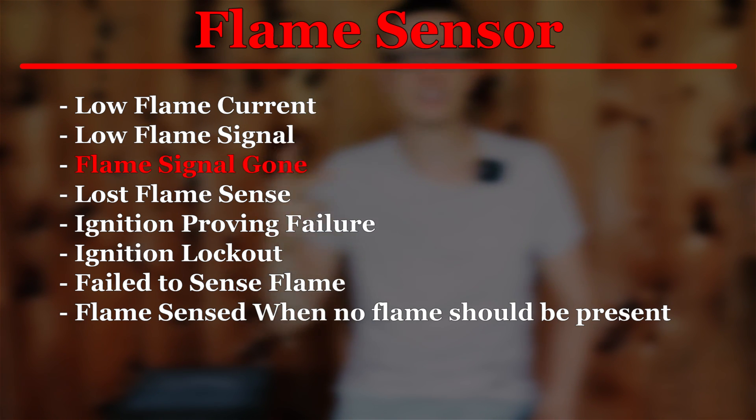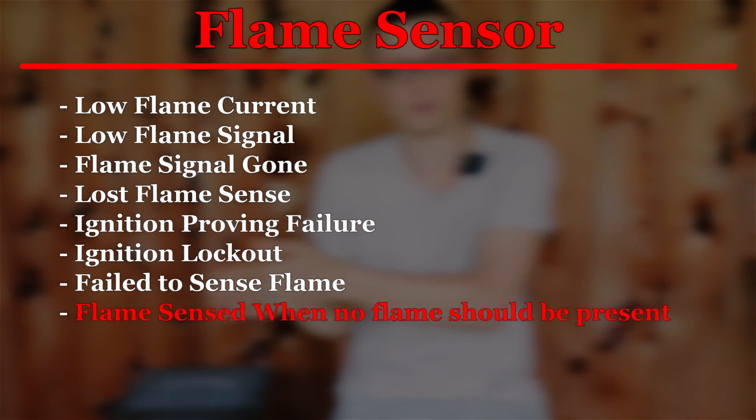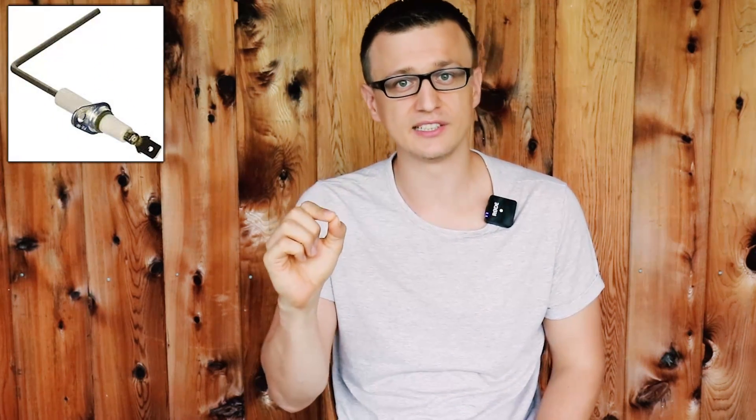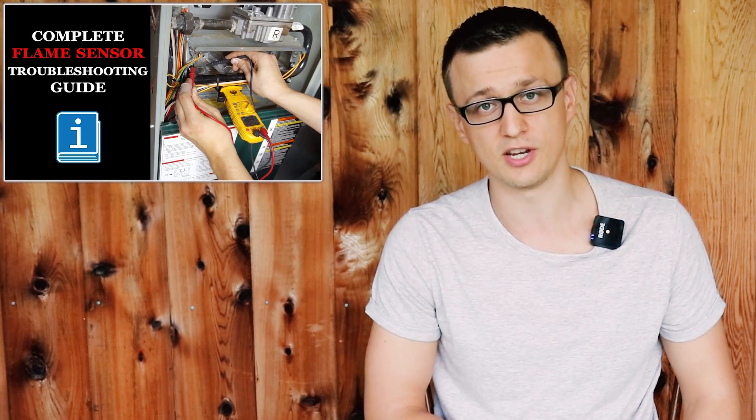The first error code I want to cover is the most common problem I run into, and luckily this one is usually the most easiest problem to fix — and that is the flame sensor error code. On different furnaces this error code will be worded differently, but here are some examples: low flame current, low flame signal, flame signal gone, lost flame sense, ignition proving failure, ignition lockout, failed to sense flame, flame sensed when no flame should be present, and so on. Most flame sensor error codes will be very similar to one of those phrases. If you are seeing a flame sensor error code, there's a good chance that all you have to do is simply clean the flame sensor rod. If you're not sure how to do that, I have a video on how to find and clean the flame sensor on a furnace. And if cleaning the flame sensor does not do the trick, I have another video where I go deeper into those flame sensor issues and talk about other possibilities that could cause this error code to pop up.